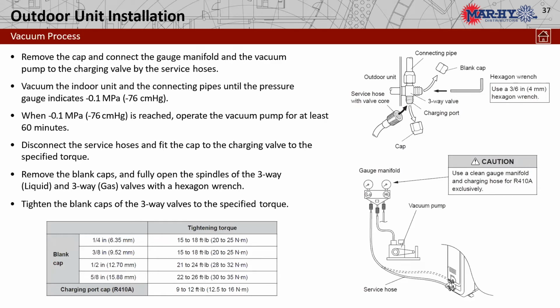So there again, the vacuum process. We're going to use all of our decent refrigeration techniques. We're going to do our good flares. We're going to put a little oil on them, tighten them up to torque specs. We are going to pressure test that at 500 pounds, make sure that we are not leaking. And then we're going to start the vacuum pump, and we will pump down to 500 microns, just our standard refrigeration practices. No difference.